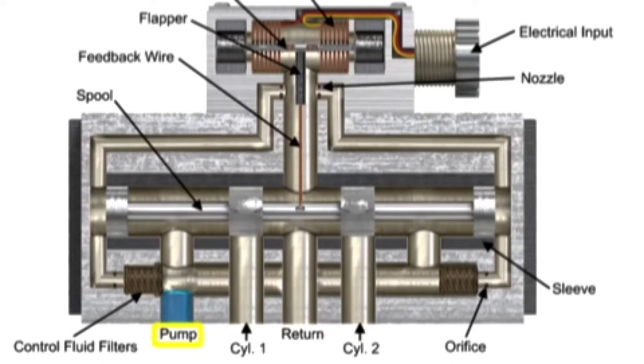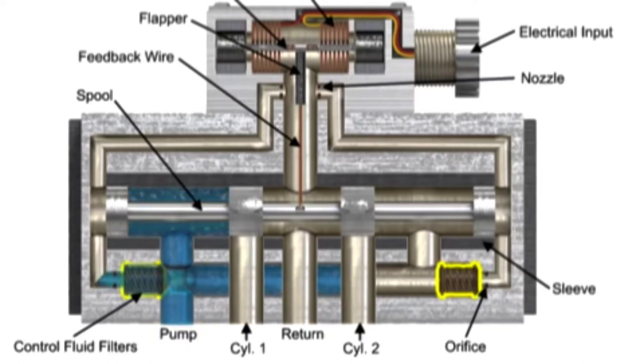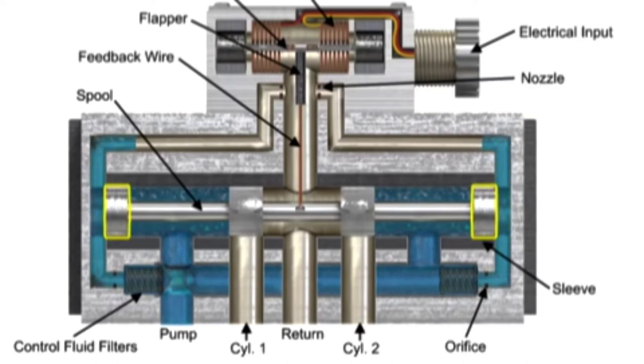Fluid from the pump inlet is tapped off through filter elements, passes through orifices past both ends of the spool, goes on to nozzles, and out to the return line.